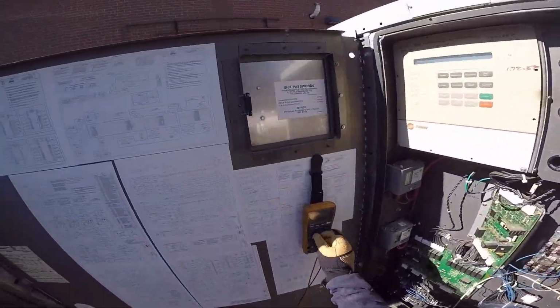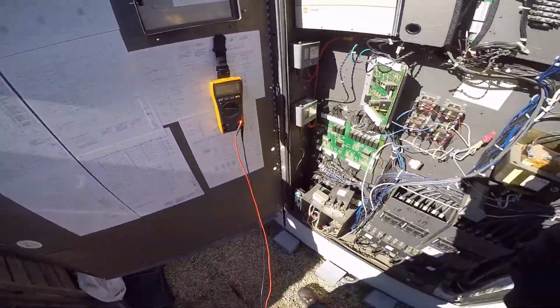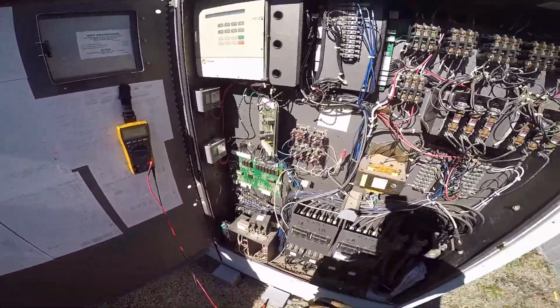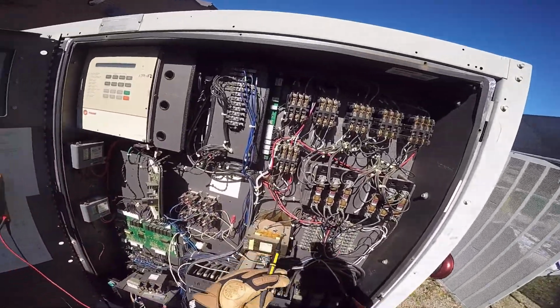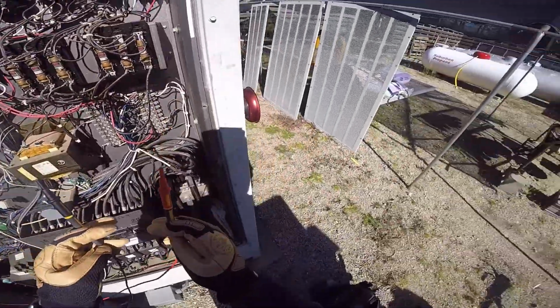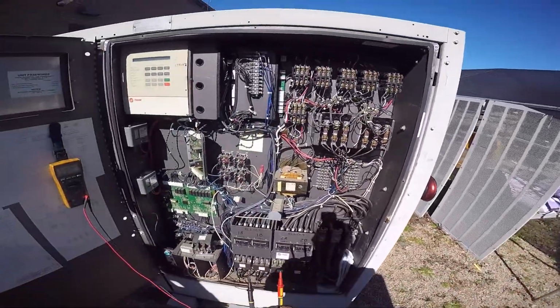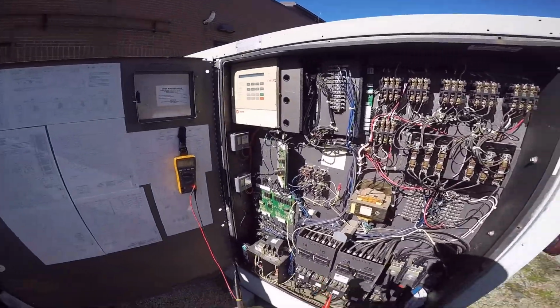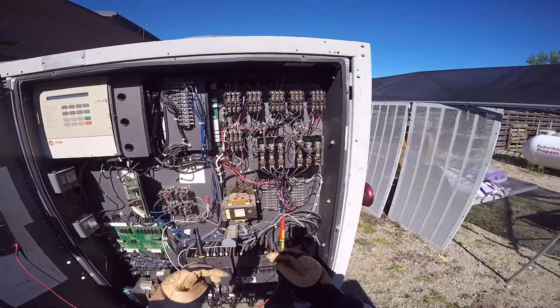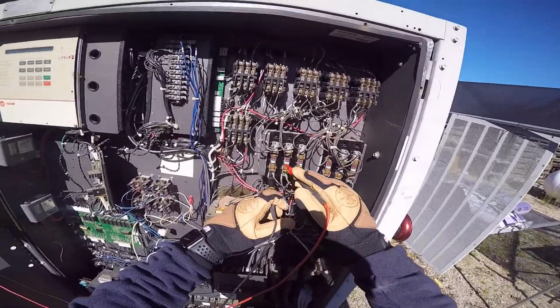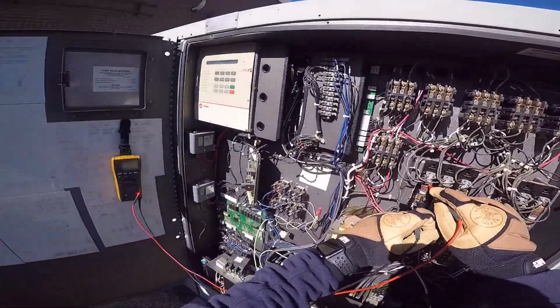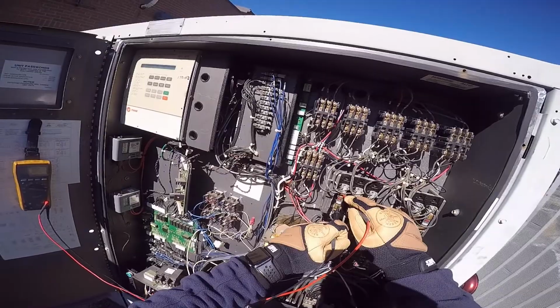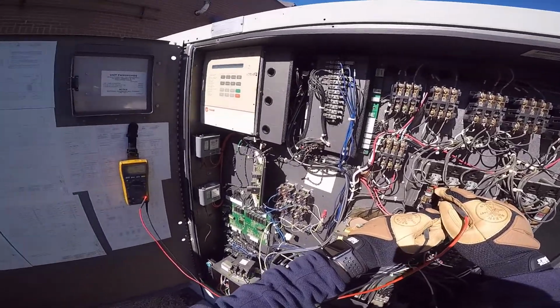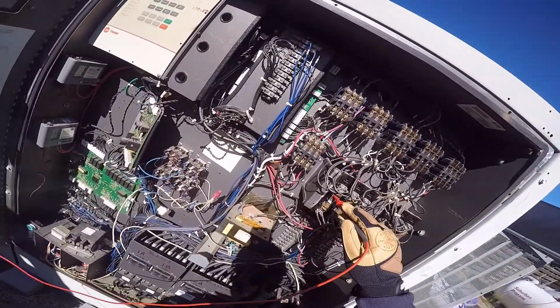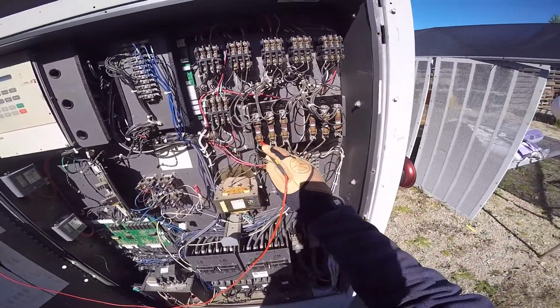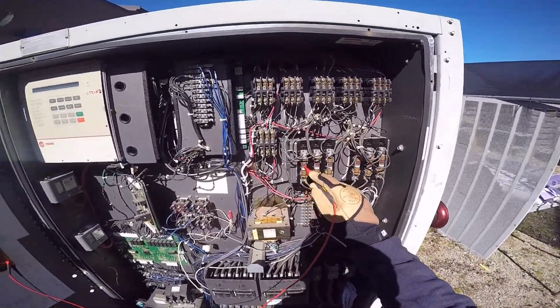I don't use the beeps usually. I stay on the volts, because remember, these two leads on this meter read the difference between each lead. That's all the meter does - reads the difference between this lead and this lead. So if I come to the top and bottom and I've got 0, there's no difference. If I've got 120 volts right here, that means the difference between the top of this fuse and the bottom of this fuse is 120 volts, which means this fuse is bad.